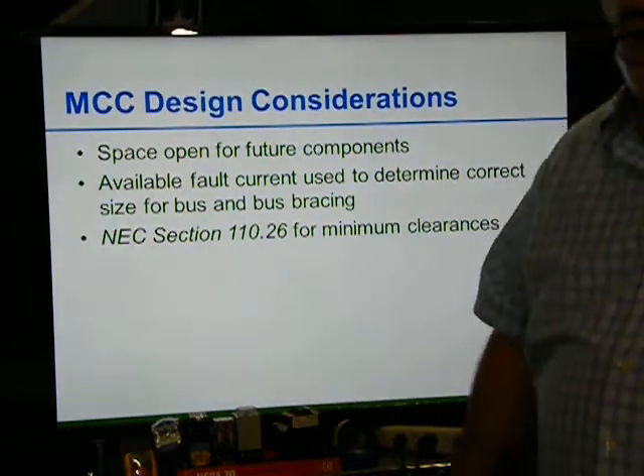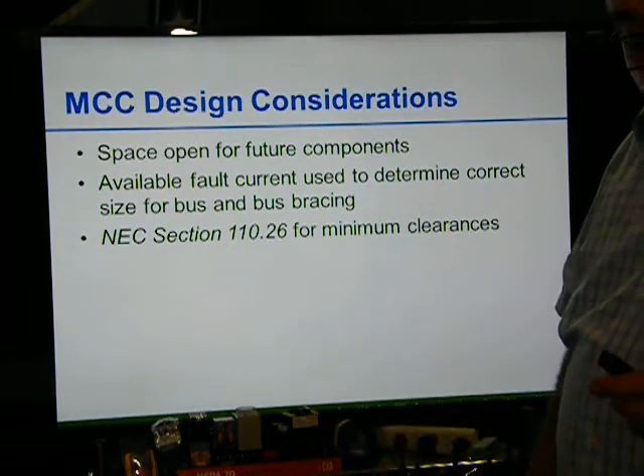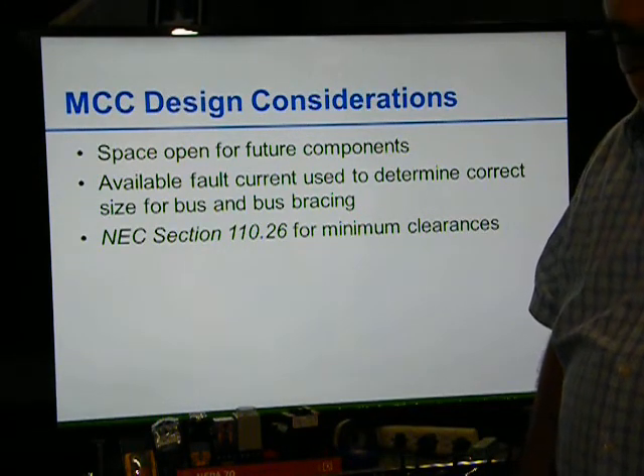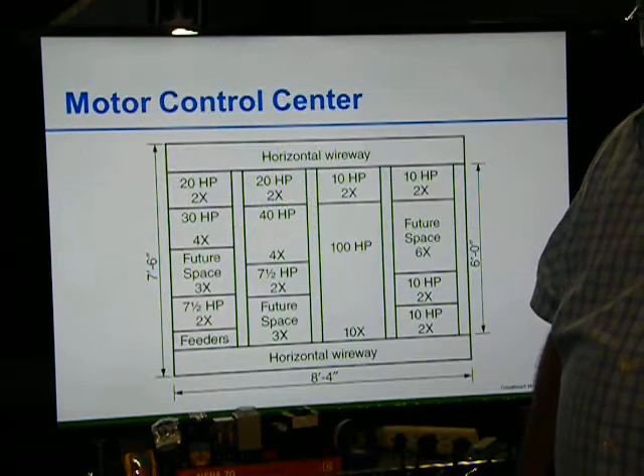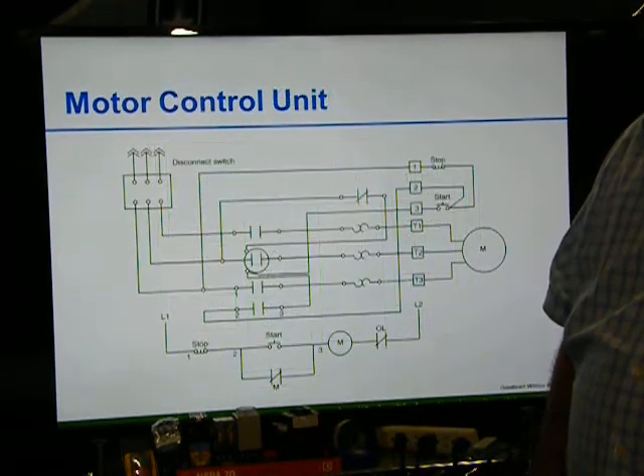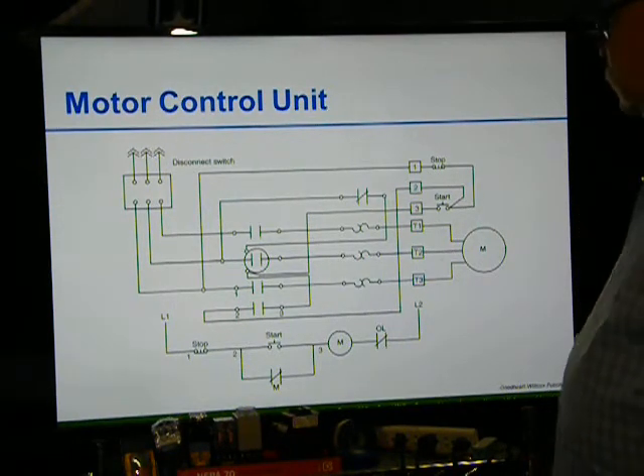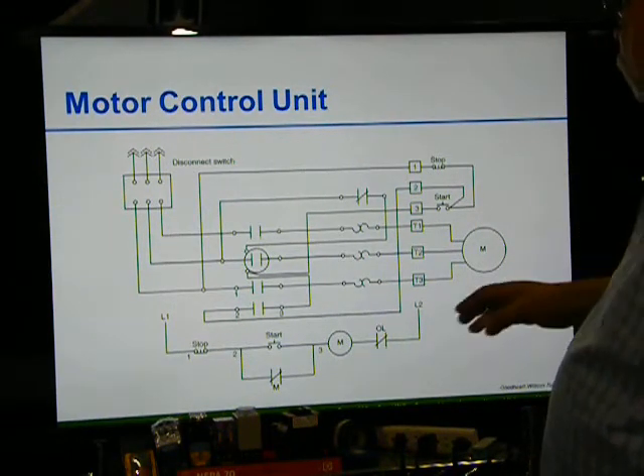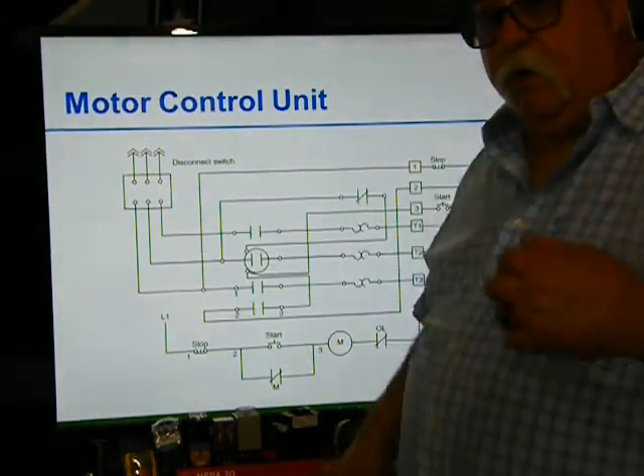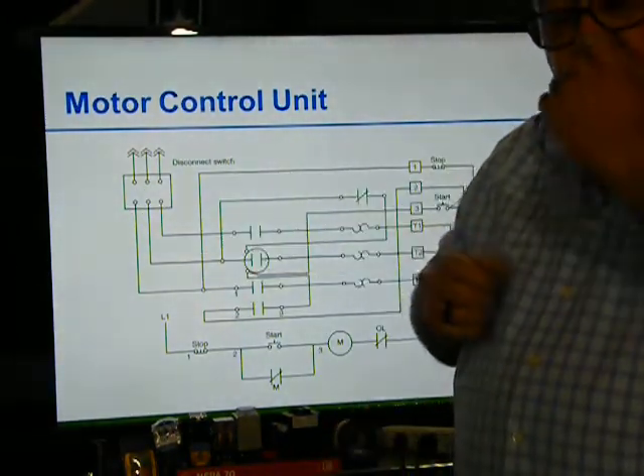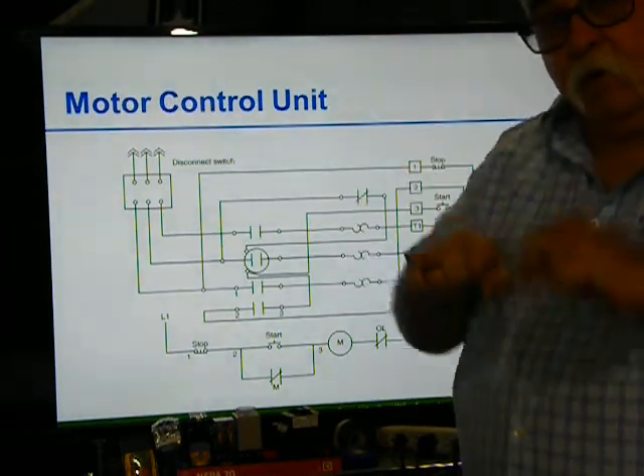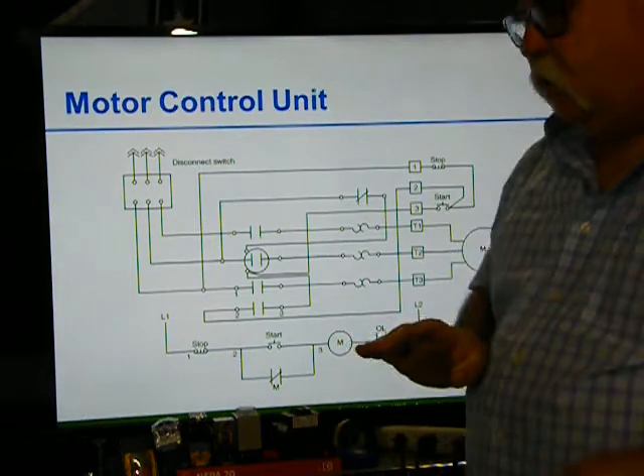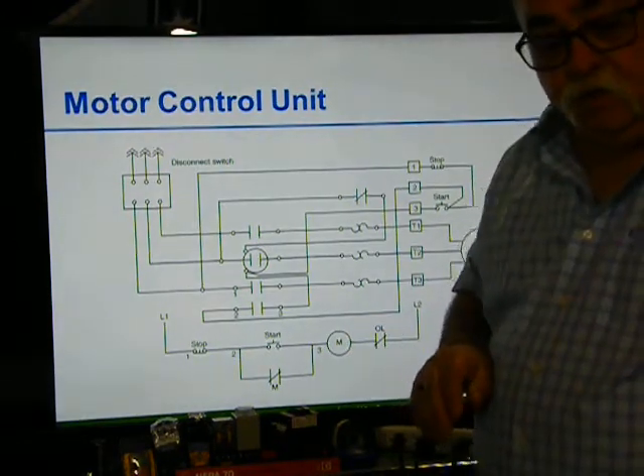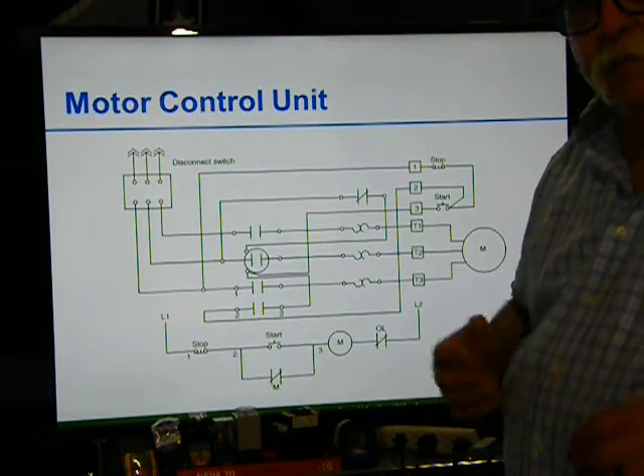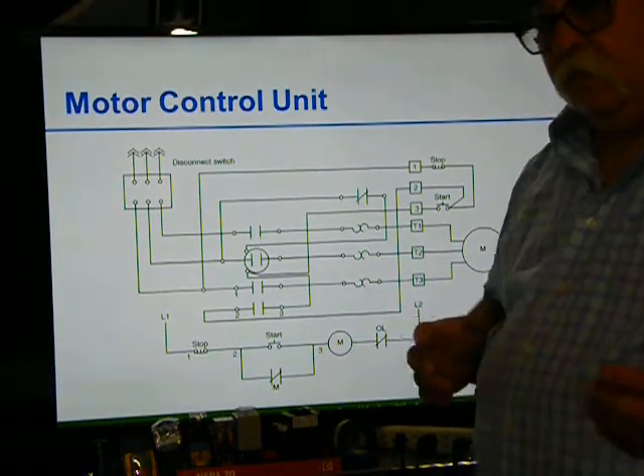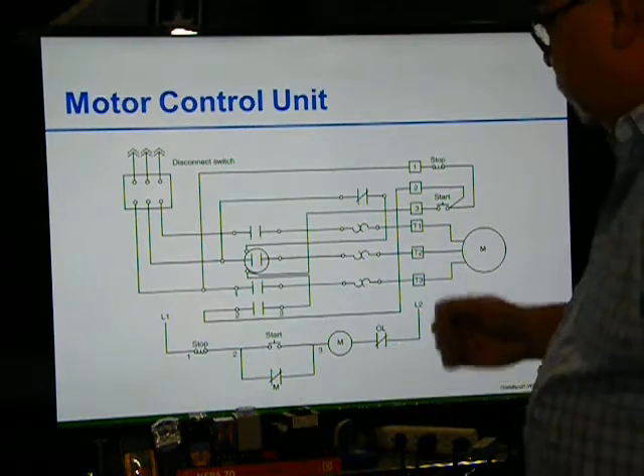So what are the clearances that you have to have? That is in Article 110.26. Okay, there's a motor control unit. Within a unit itself, here's the disconnect. It's going to have a breaker or fuses, and the bucket usually pulls out, so you not only turn it off, but you can pull it out so you can work on it, and it kills everything. Remember those pictures that I showed you, the guys that were working inside of one, and it blew up. Two guys trying to work in an area that big, and it blew up in their faces.